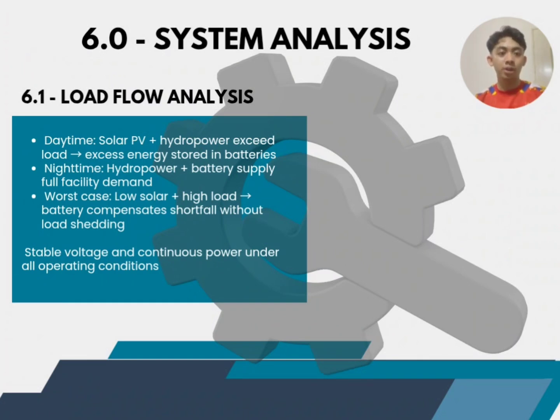Okay, first, load flow analysis. During the day, solar PV and hydropower produce more power than the facility needs, so extra energy is stored in the battery. At night, hydropower and the battery supply the load when solar power is not available. Even in the worst-case condition, the battery can support the system without load shedding. This shows that the system can supply stable and continuous power.